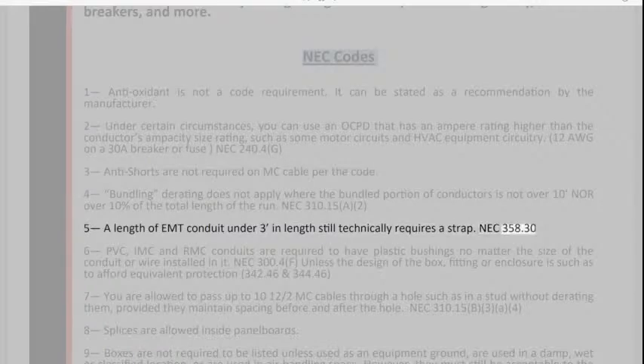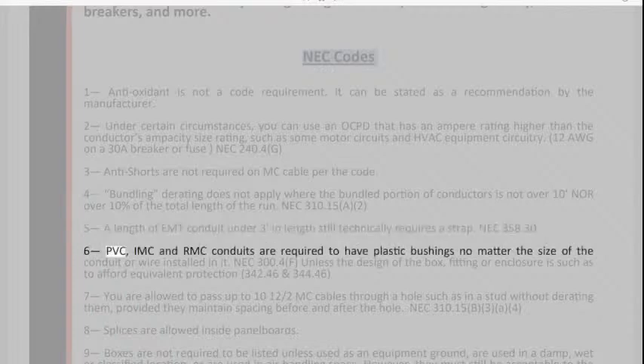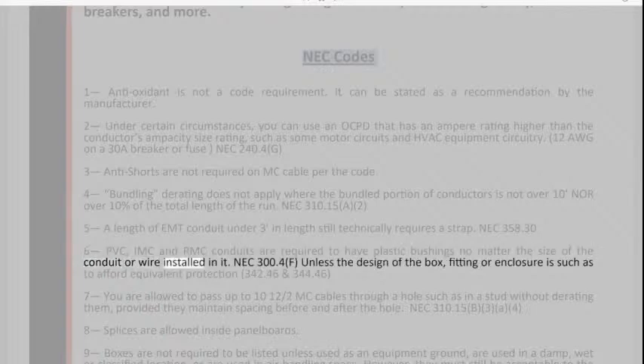NEC 358.30. 6. PVC, IMC and RMC conduits are required to have plastic bushings no matter the size of the conduit or wire installed in it.